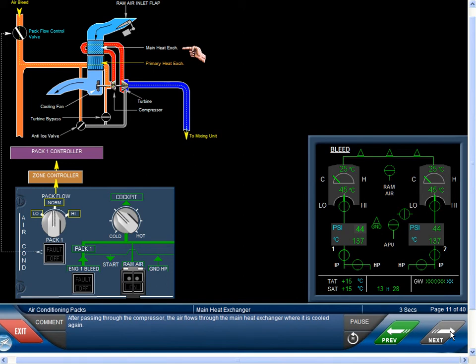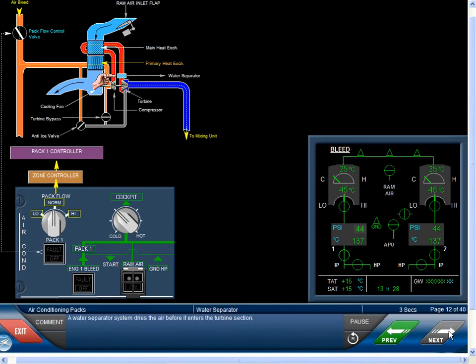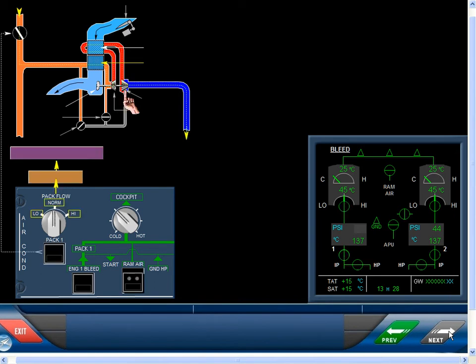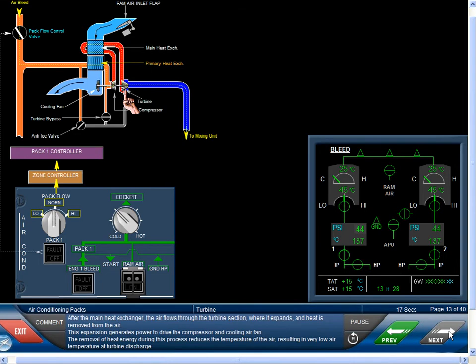After passing through the compressor, the air flows through the main heat exchanger, where it is cooled again. A water separator system dries the air before it enters the turbine section. After the main heat exchanger, the air flows through the turbine section where it expands and heat is removed from the air. This expansion generates power to drive the compressor and cooling air fan. The removal of heat energy during this process reduces the temperature of the air, resulting in very low air temperature at turbine discharge.